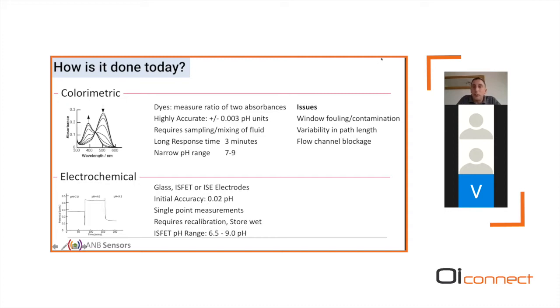On the colorimetric, window fouling, which gives you a variability in path lengths, and you can get blockage to your flow channels. And then on the electrochemical, as they're a single-point measurement, there is no smartness there in terms of the way they operate during deployment. There are storage issues. They have to be stored wet. They can't be stored dry, so you have to keep them wet right until you put them in the water. Reference electrode drift means that they require recalibration quite frequently, and I know a lot of the ones that are used today have to be sent off for calibration once a year at least.